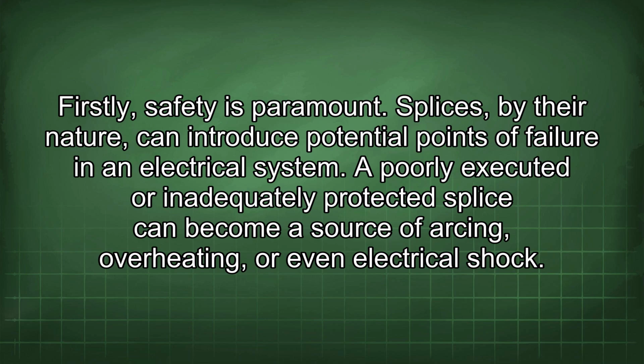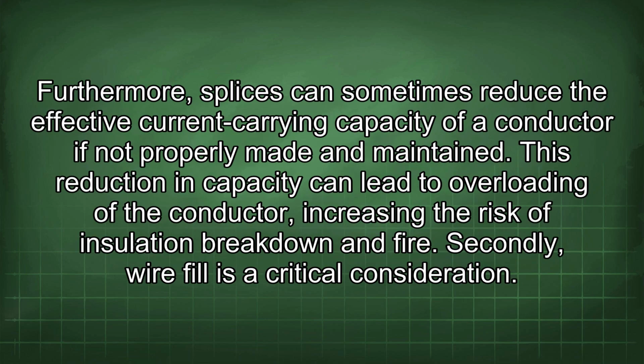Firstly, safety is paramount. Splices, by their nature, can introduce potential points of failure in an electrical system. A poorly executed or inadequately protected splice can become a source of arcing, overheating, or even electrical shock. Furthermore, splices can sometimes reduce the effective current carrying capacity of a conductor if not properly made and maintained. This reduction in capacity can lead to overloading of the conductor, increasing the risk of insulation breakdown and fire.